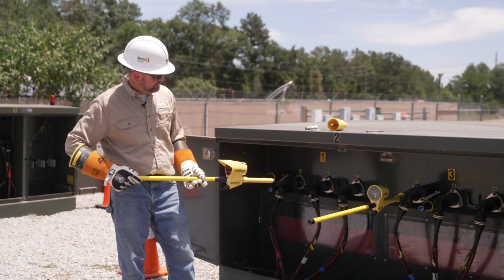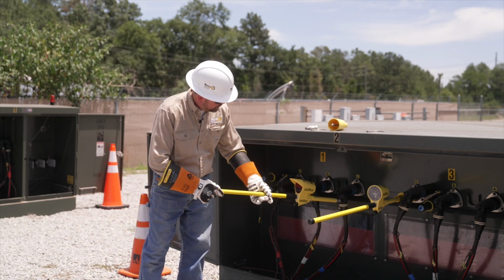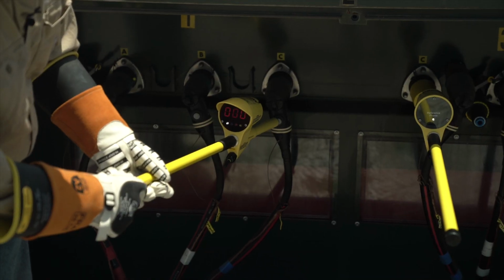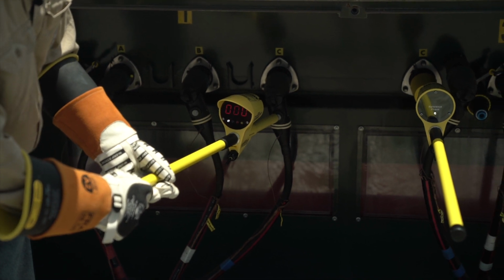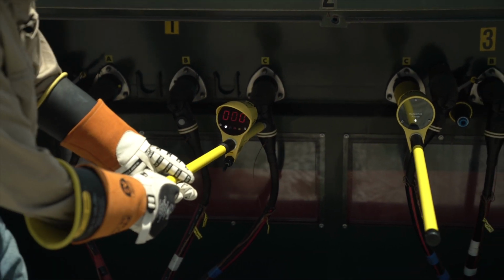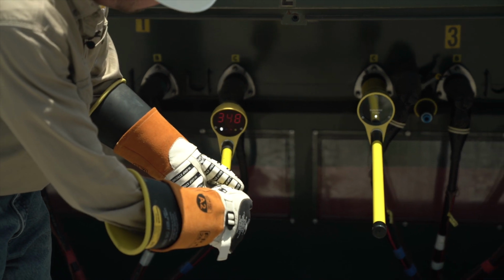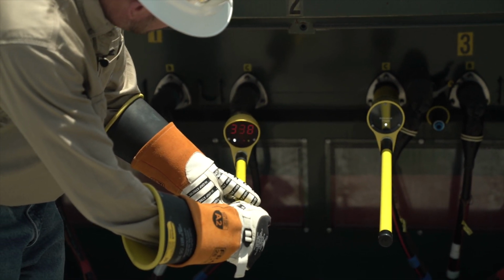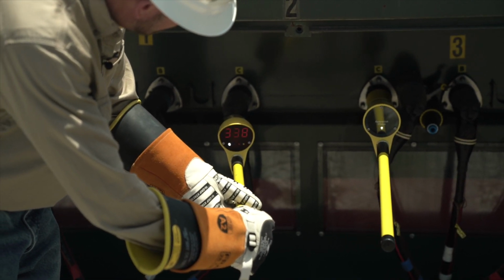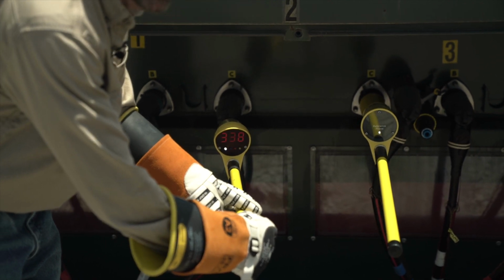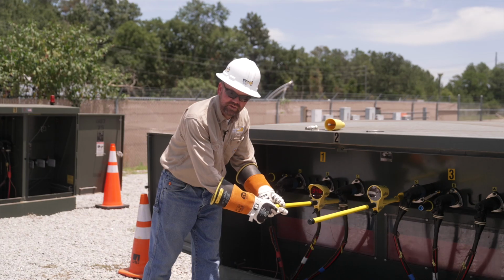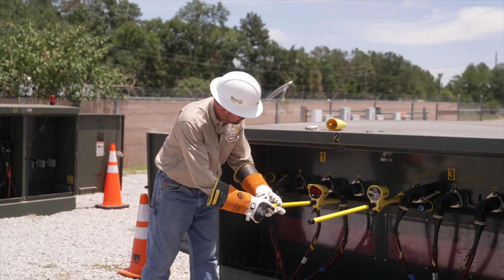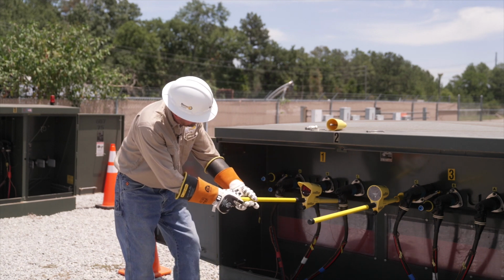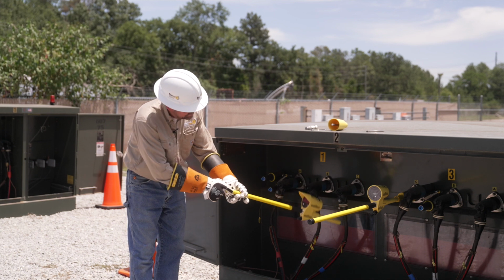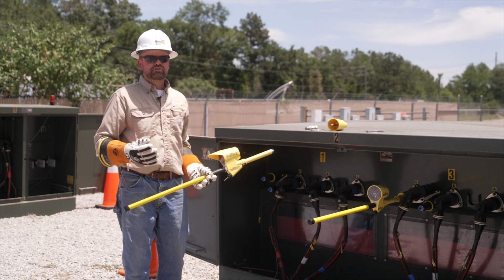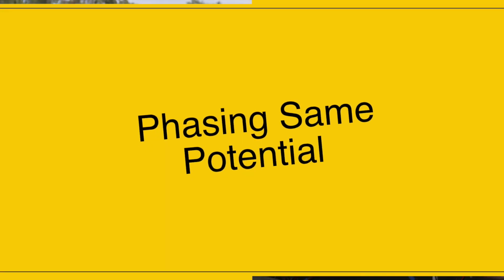In other words, if I come in here away from the reference probe, I get my white light, a good white light, a 0 reading. If I start moving the housing towards the reference probe, you'll notice that number gets out of whack, so to speak. It's not a reliable reading because I have a flashing yellow light now, so I don't like that. It's not making me comfortable. So really all I have to do is just move my housing away from the other housing, try to get at least 2 feet away, and get a reliable reading.